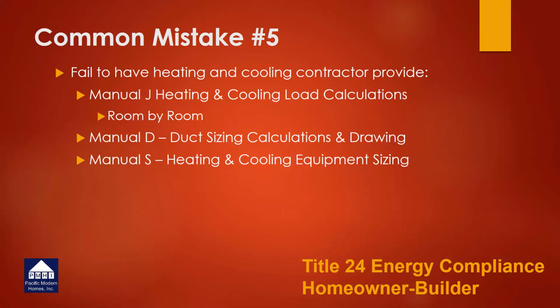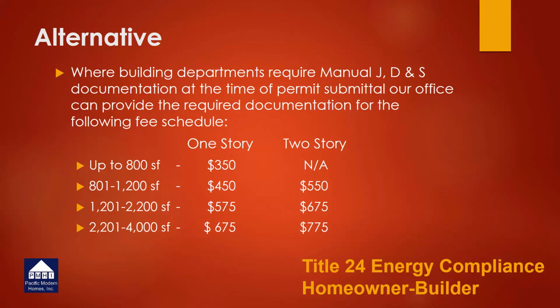Historically, I have instructed owners to have the contractor that's installing your heating and cooling system do this documentation. However, some building departments are not allowing this portion of the work to be deferred. So if you haven't hired a mechanical contractor to do this at the time that you're submitting to the building department for your permit, you may find that the building department is going to require it anyway. If you encounter that specific issue, our office has provided an alternative to Pacific Modern Homes where we can put together and provide you the Manual D, the Manual J, and the Manual S documentation for the building department.